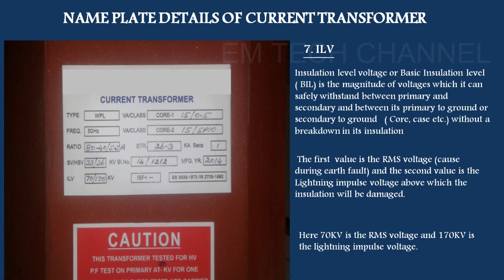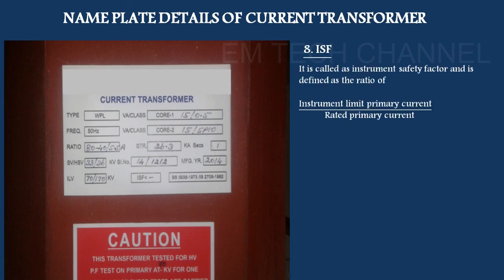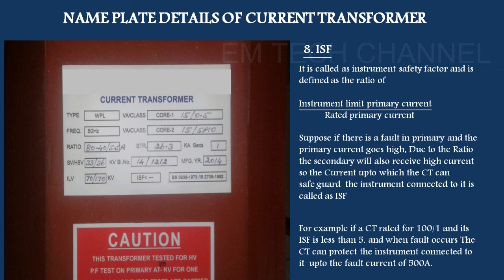ISF is the instrument safety factor. This is the ratio of instrument limit current to rated primary current. If there is a fault in the primary, the primary current increases. The CT secondary also increases proportionally. To protect the connected instruments, the ISF limits this. With a lower ISF value, the instrument is better protected from high fault currents, so instruments like meters are not destroyed during fault conditions.